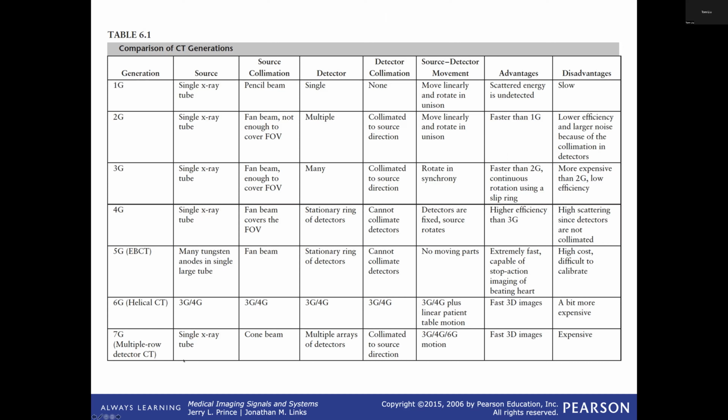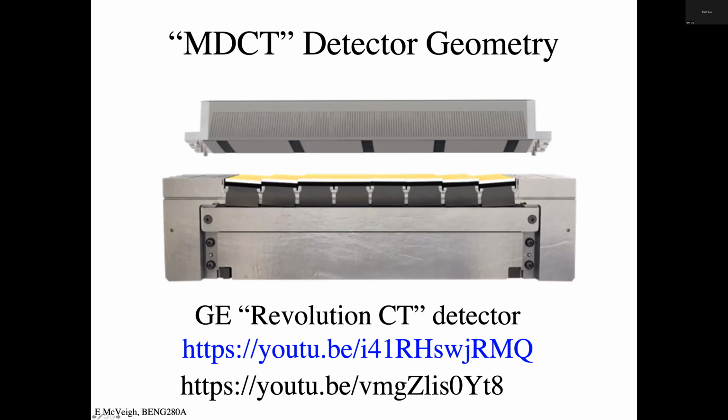The next thing coming, and we won't talk about this though, is direct X-ray detection with photon counting detectors. That's what's going to happen next in CT. I welcome you to go to these websites. They have beautiful animations of exploding scanners, so you can see the makeup of the components of the scanner. Here, we looked at a detector here.